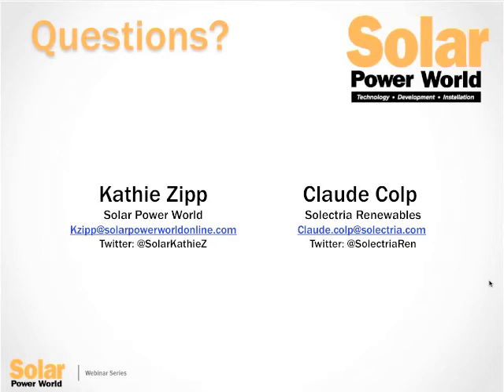What I would do, based on the feedback and the research that I've done, is use a very low tech way of accomplishing the rapid shutdown sequence, using an AC feed to something like a 30 amp disconnect, for instance, or a 60 amp disconnect. From there, you feed the power to your Arcom combiner boxes, and the rapid shutdown sequence would begin by flipping the AC power to the Arcom box out. And we recommend placing that in a location that can be readily accessible and seen by first responders coming in. It's kind of like an airbag.